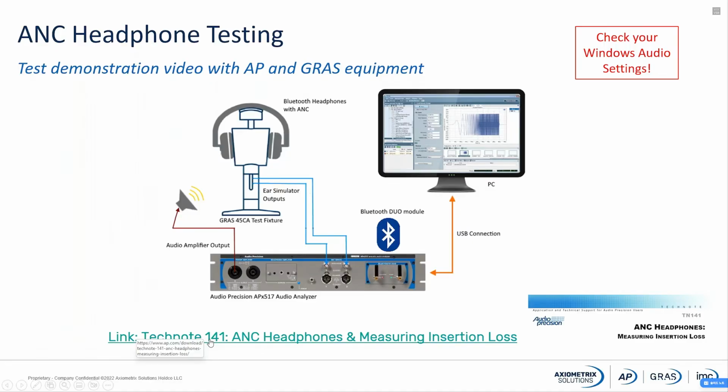You can open the file in demo mode, and then you will be able to see the whole sequence, and you can see exactly how first I measure the noise, then I measure the noise with the signal, in both open ear situations, and with those two results, I can calculate the signal to noise ratio.